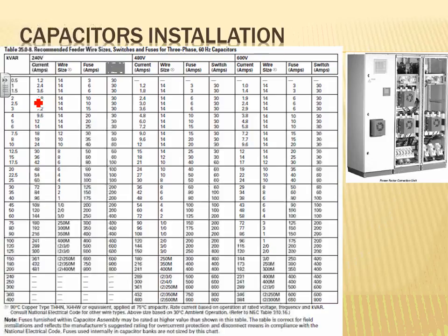Then it goes even further than that. There's another sheet. This is again from Cutler Hammer. Here's my 480. Look what happened. See the same 10 kVAR that I just sized. Look what it tells you. Here's how many amps that baby's going to draw out of the system at 480 three phase. Here's the size of the wire they recommend. Would you use anything less than 12? No. So they said 14, but we never use anything less than 12. And this is the size of the fuse that you can put on it. And this is the size of the disconnect directly from this sheet. The disconnects are sized based on 1.35. The overcurrent protection devices, they're sized based on 1.35, and they go up on these sheets. I checked a few of them. I typically go down unless I know otherwise. But if you have these sheets, guys, from Cutler Hammer, I wouldn't hesitate.